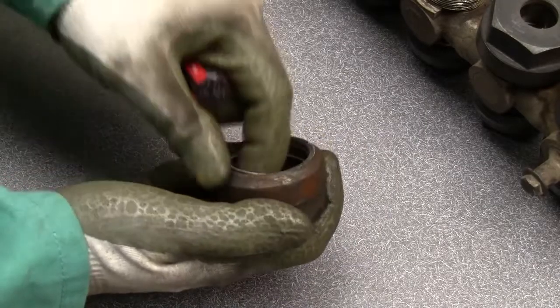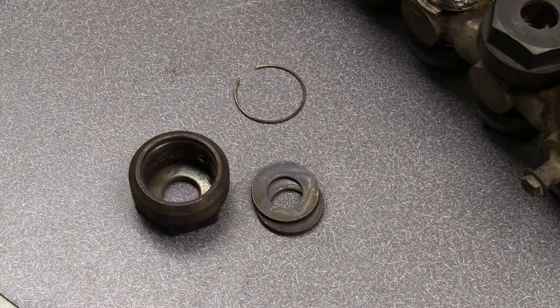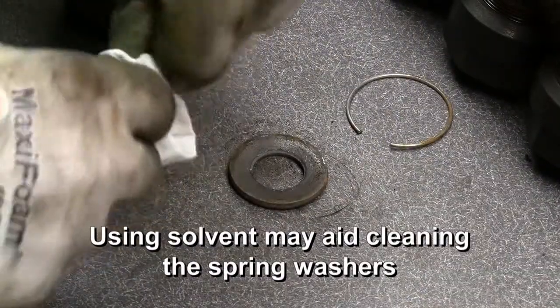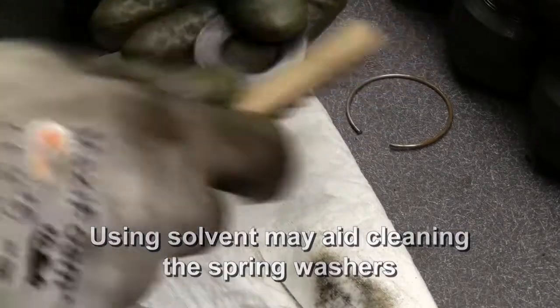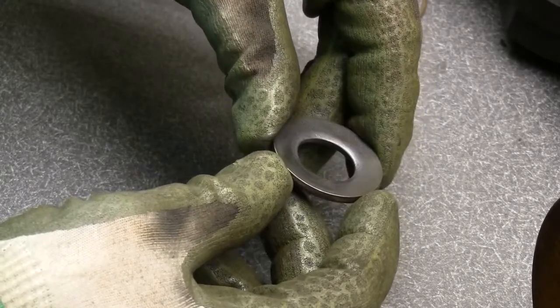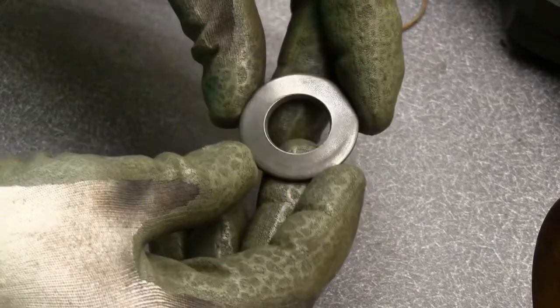Tap the nut open side down to dislodge the spring retainer and Belleville washers. Save the spring retainer. Clean the Belleville spring washers. Depending on your unit, you may have 2, 6, or 8 spring washers. Inspect them for cracks, pitting, or corrosion. If the washers are damaged, they must be replaced because the spring function is critical.